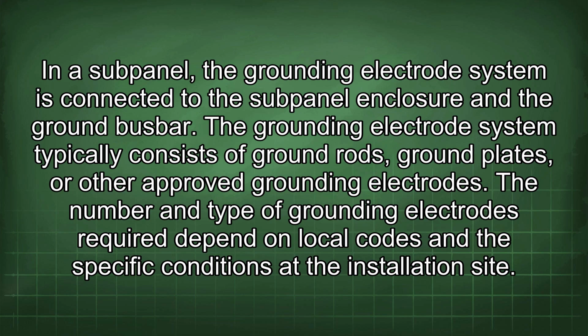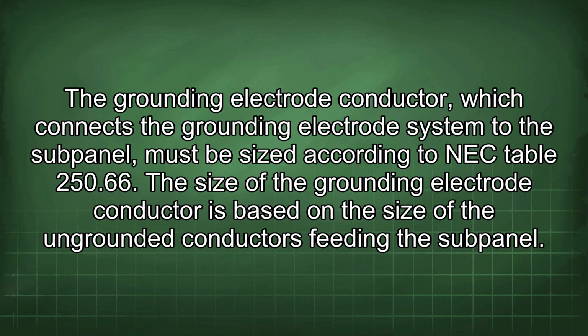The grounding electrode system typically consists of ground rods, ground plates, or other approved grounding electrodes. The number and type of grounding electrodes required depend on local codes and the specific conditions at the installation site. The grounding electrode conductor, which connects the grounding electrode system to the subpanel, must be sized according to NEC Table 250.66. The size of the grounding electrode conductor is based on the size of the ungrounded conductors feeding the subpanel.